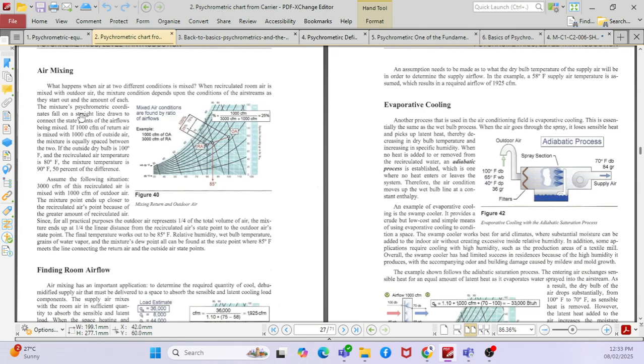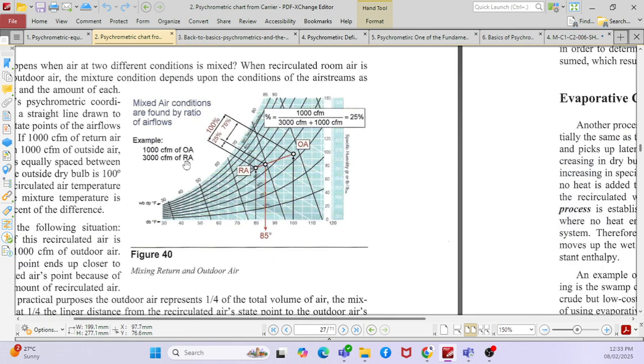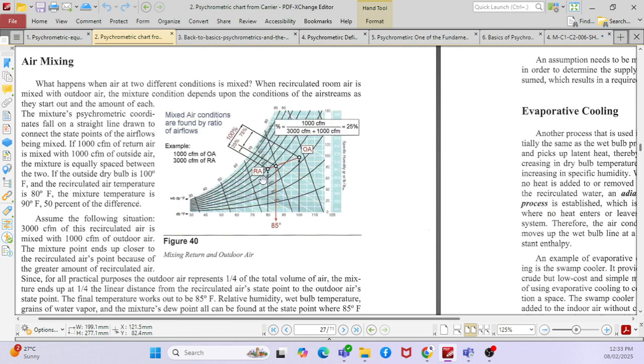Okay, then when you say that air mixing, what you are doing? Mixing the air, outside air and return air. So when you design the AHU, you have an outside air and return air. Somebody will ask for mixing boxes, right? Yes, sir. When you have mixing boxes, you should find out what is the outside air condition and what is the design return air condition. Based on that, how much energy or how much percentage of moisture, what is the change in the properties, you can find out.